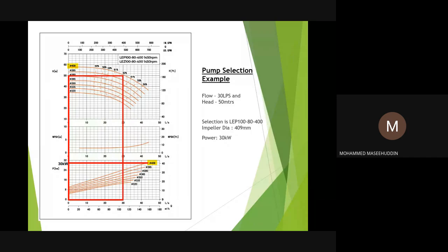But if you go to the end of the same curve and draw a corresponding line to the motor rating, it's coming to 30 kilowatts. So that's the reason why we have selected 30 kilowatts, which is required to run this pump, even though the absorbed power is only 24 kilowatts for this particular selection. Hope it is clear for the pump selection.